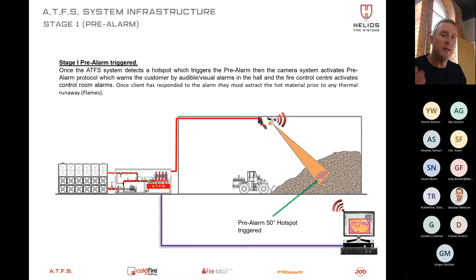In most cases on MRFs, we do 90 and 150. So here now we've given the client the opportunity to check. In that case, it might just be a piece of hot material that's come off a shredder, we can forget it, take that piece of hot material away, and we carry on. If for whatever reason we then get escalation in temperature, and we then hit 150 degrees at 50 millimeters by 50 millimeters, the camera system will then send the coordinates to the cannon system and to the pump station to react. And this happens within seconds.